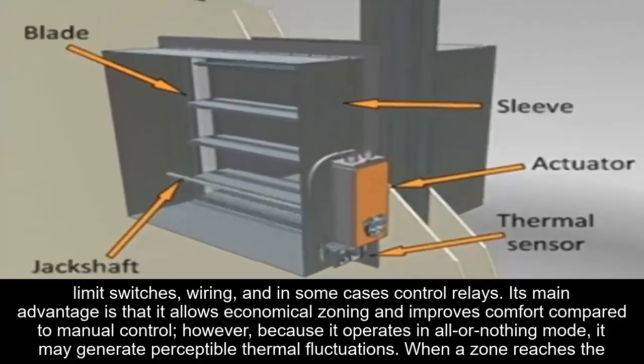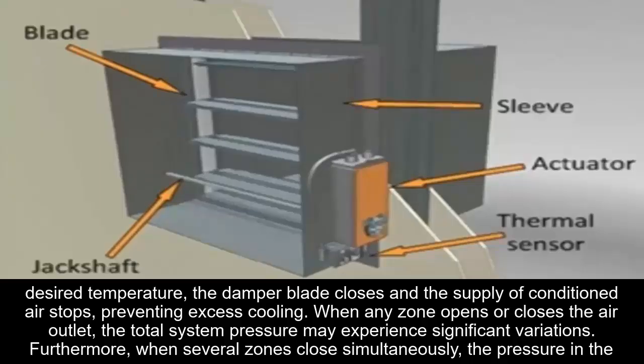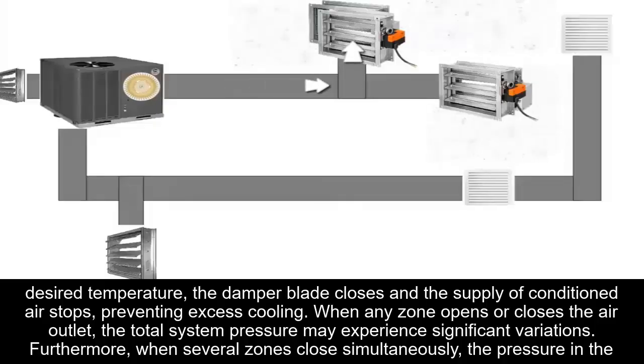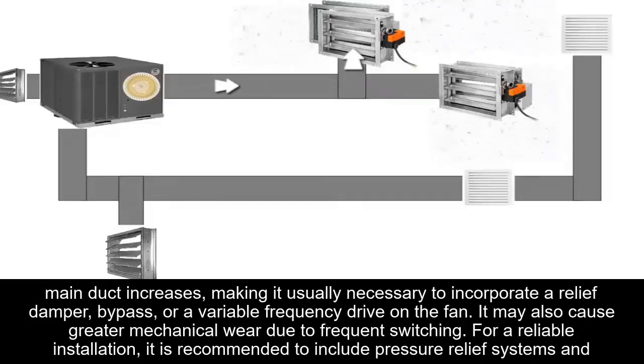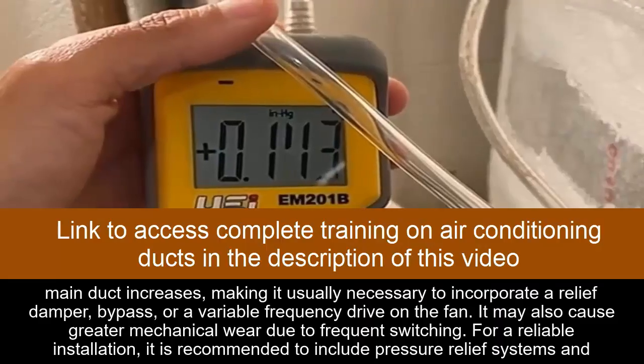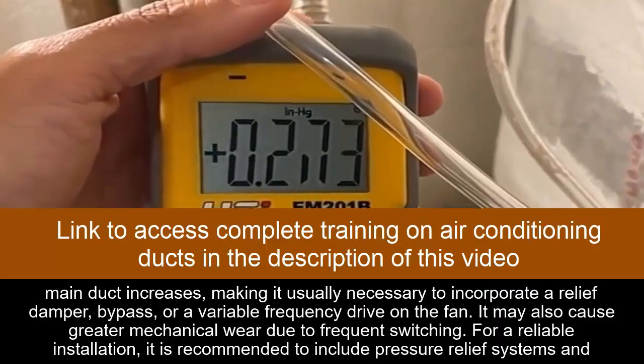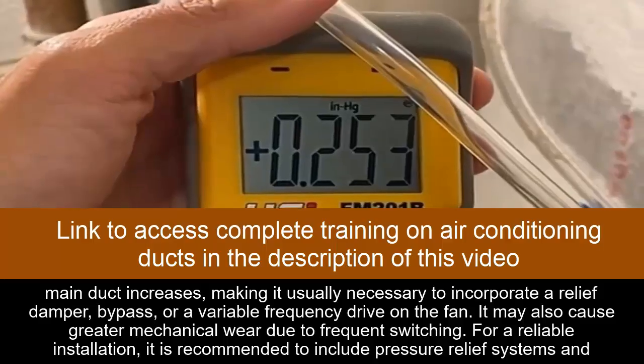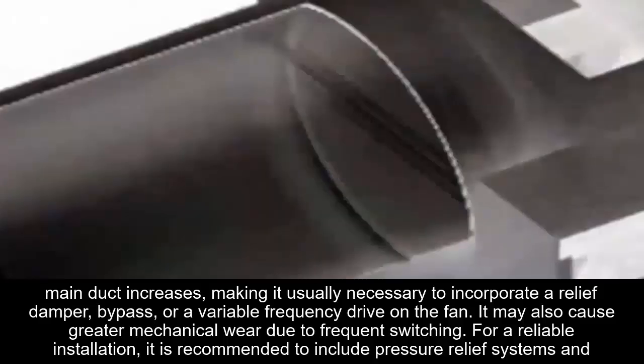When a zone reaches the desired temperature, the damper blade closes and the supply of conditioned air stops, preventing excess cooling. When any zone opens or closes the air outlet, the total system pressure may experience significant variations. Furthermore, when several zones close simultaneously, the pressure in the main duct increases, making it usually necessary to incorporate a relief damper, bypass, or a variable frequency drive on the fan. It may also cause greater mechanical wear due to frequent switching.